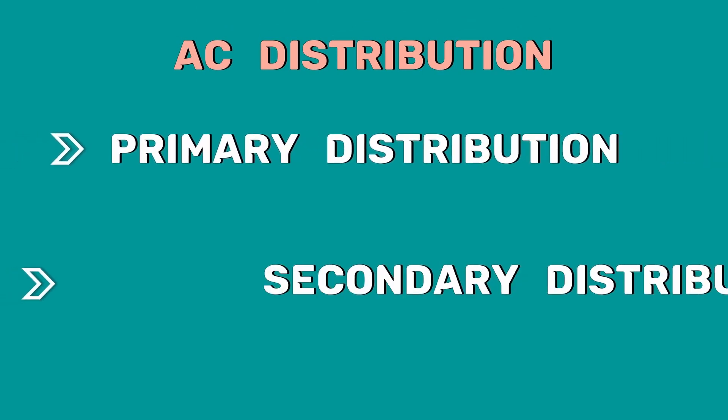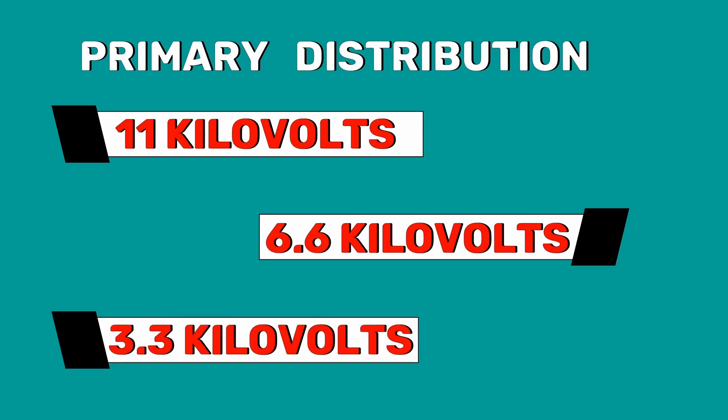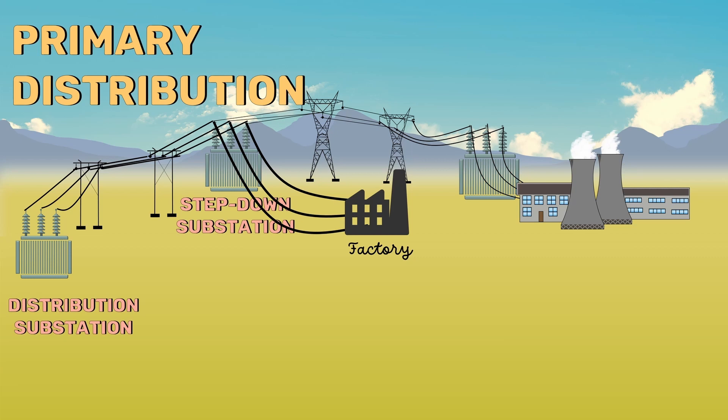The AC distribution system is classified into primary distribution system and secondary distribution system. The primary distribution system is the part of the AC distribution system which operates at voltages somewhat higher than the general utilization voltage. The most commonly used voltages are 11 kV, 6.6 kV, and 3.3 kV. Due to economic consideration, the primary distribution system is carried out by a three-phase, three-wire system. Primary distribution handles large consumers such as factories and industries, and also feeds small substations where secondary distribution is carried out.